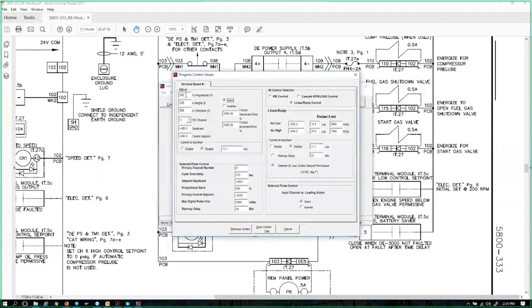From that point, if I want to slow the response of the valve or my action a little bit, I will raise this number slowly. If I need to speed it up further, I will lower this number. Integral is a way to fine-tune it. Generally, unless I'm having some issues, you'll see me never mess with it. Derivative, same thing. You'll see me leave it at 999. The biggest thing is proportional on our system.